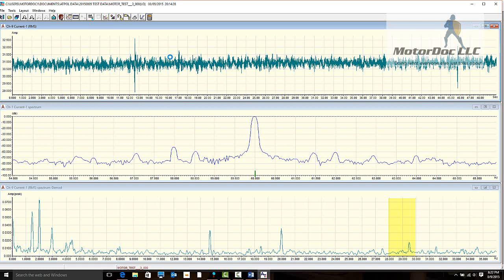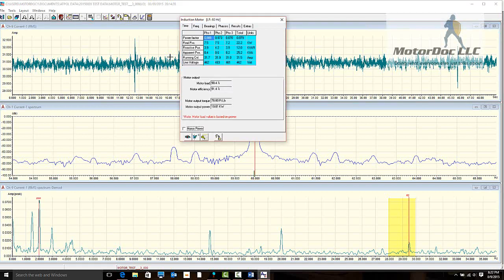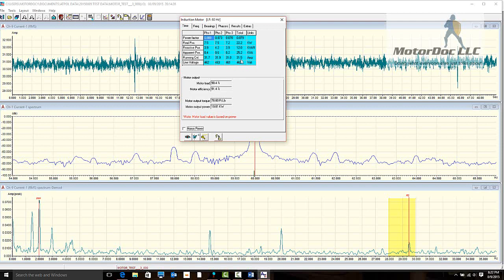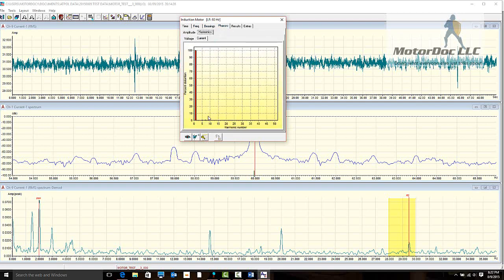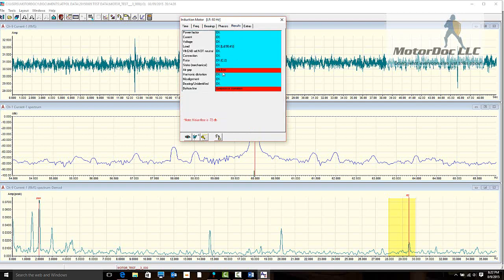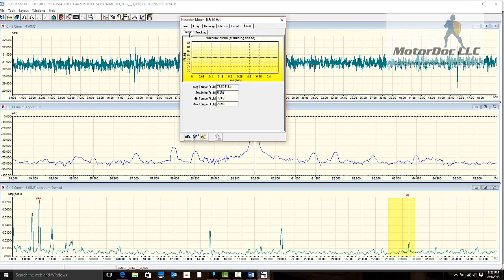We are looking at a 90% load, 91.4% efficiency, which was found by the Department of Energy to be relatively close, within a half to 1% of the actual efficiency in this particular software. Here's all my loads and my current. This is a 34.5 amp machine, so I am very near full load. Frequencies again, bearings all okay, phasors again, results, static eccentricity as well. And then finally any type of torque-related issues, and I don't see much there.